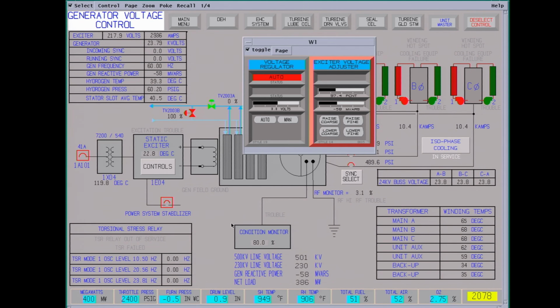So you have your balance authority operator. Their job is to coordinate with the plants how much to put out to try to maintain a uniform 60 cycle. A lot of breakers are set to trip about 58 hertz. The reason they do that, you can overflux your transformers, the high voltage and low frequency, and it creates too high of a magnetic flux. So the magnetic flux cannot go through the iron core in the transformer. It overloads it. So it looks for another path and it'll start going through the metal frame, creating a tremendous amount of heating and damage. So these are designed for 60 cycle, and they pretty much have to run at 60 cycle. And that's why your voltage is critical and your frequency is critical. You can overflux equipment and do a lot of damage.